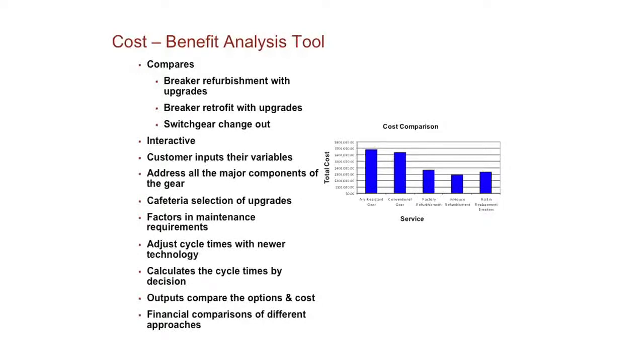Let me back up one second. One of the things you need to understand is there's a cafeteria selection of the upgrades. For example, if you told me you want remote racking done on your switchgear, it'll take remote racking and apply it to the existing breaker refurbishment option, the breaker retrofit option, and the switchgear changeout. So you're comparing apples to apples. If you've got one upgrade, you've got that upgrade across all of them.